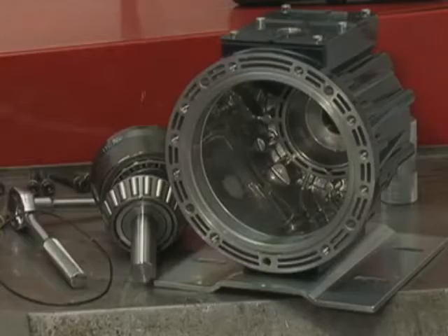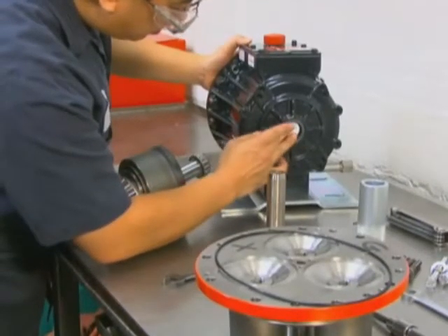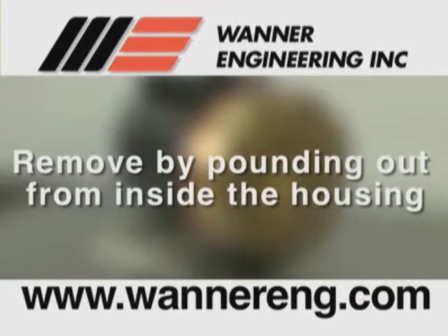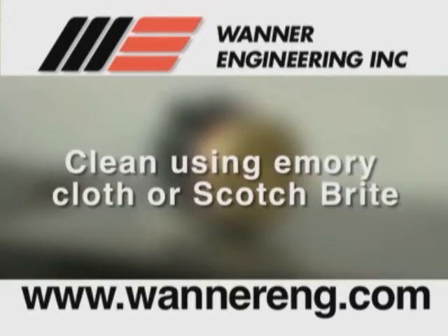Now we will see how to reassemble the pump housing and cylinder housing. Please note: inspect the shaft seals before continuing. If they look damaged in any way, replace them. Remove by pounding them out from inside the pump housing. Both seals should be replaced at the same time. Clean the seal bore in the housing using emery cloth or Scotch Brite.